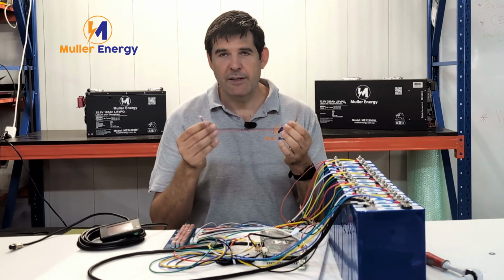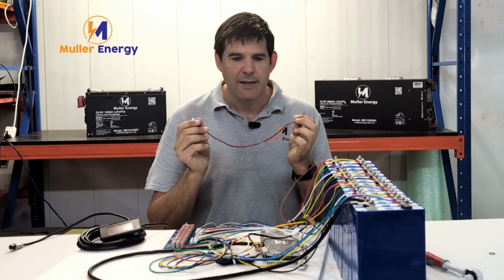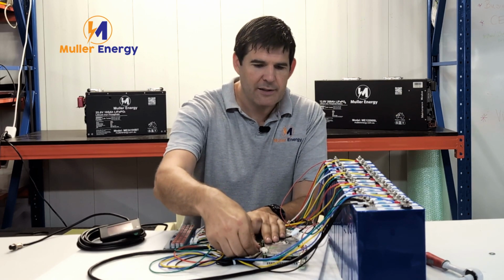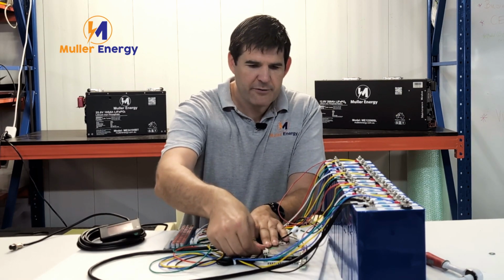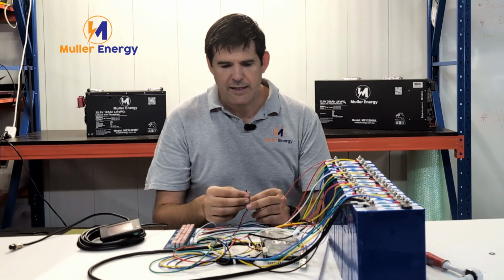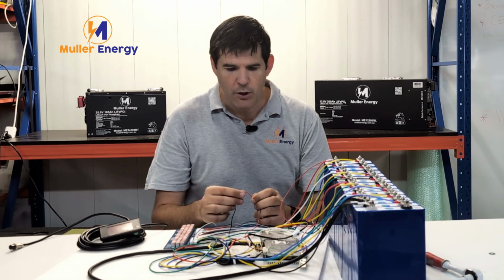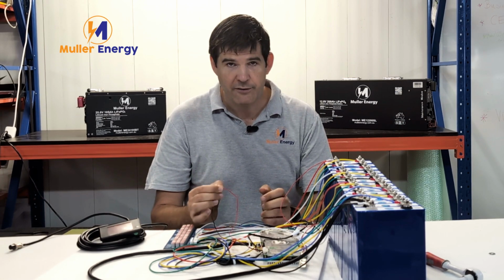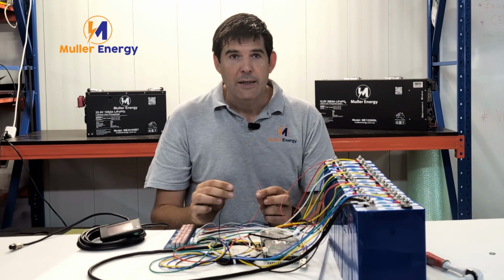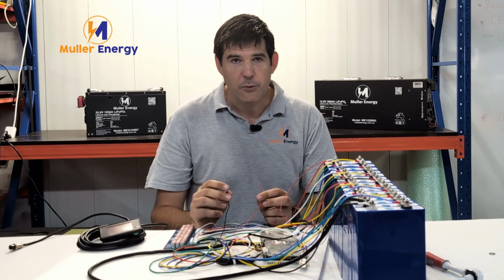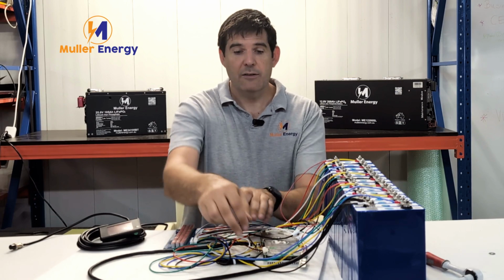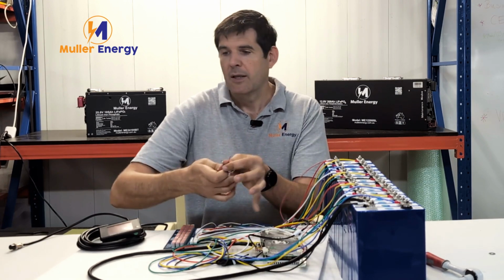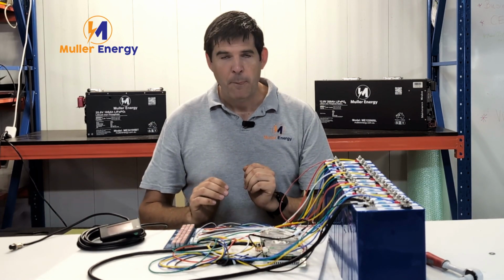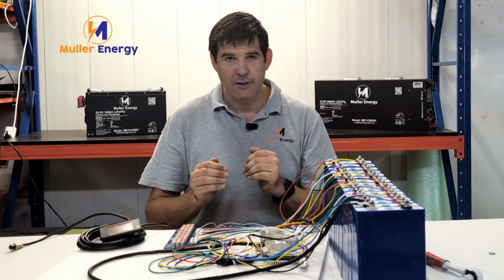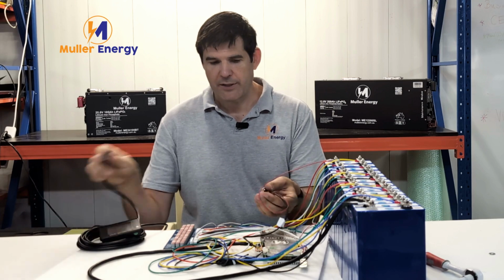The other one is a discharge switch. We can plug that in where it says discharge switch on the BMS, meaning the BMS will only discharge when these 2 wires are connected. This is the default out of the box, but I actually recommend getting rid of this cable because there's an override, and while it's great to have a BMS with a disable, we have another way of doing that.